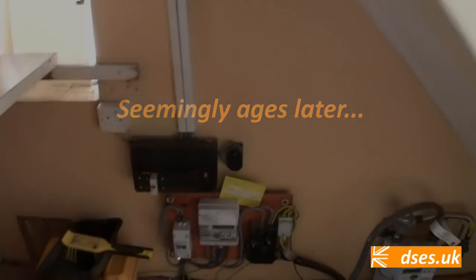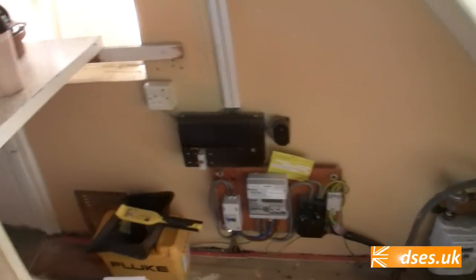The source of the installation is interesting. We did an EICR here a few weeks ago. It wasn't too bad, but there's a problem on the socket circuit. The IR wasn't where we wanted it, there was an R2 out of tolerance, something like that, and the earth on the outside. As far as the sockets go, we'll put a bit of time into seeing if it's fixable, and if not, we'll just pull in new cable while we've got the floors up.